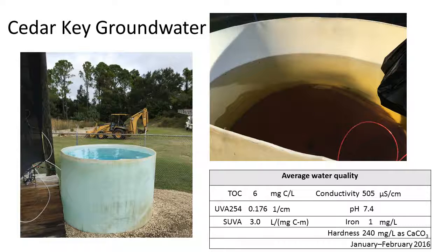So originally, some of this we didn't anticipate, right? So the intermittent operation. Also, we didn't anticipate the iron problems. I mean, we knew they had iron out there, but they have a lot more iron. Part of it was because, in the past when we worked with this water, we'd bring it back to the lab, focused on the organics and other pieces, not really thinking about the iron. But once we were there, right? So we have now about a 1,000-gallon tank. And that 1,000-gallon tank can get us through a full day of operation. And so the operators will fill this tank for us the day before we want to do experiments, so that we always have enough water to operate the next day.